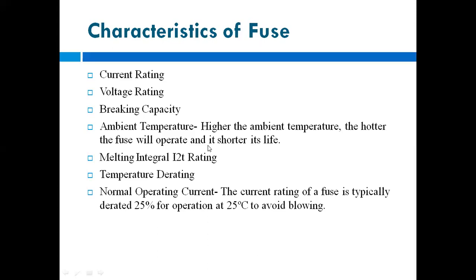We know due to oxidation there is deterioration of the fuse element, but due to continuous heating, due to ambient temperature, if that ambient temperature increases, then also the life of your fuse decreases.